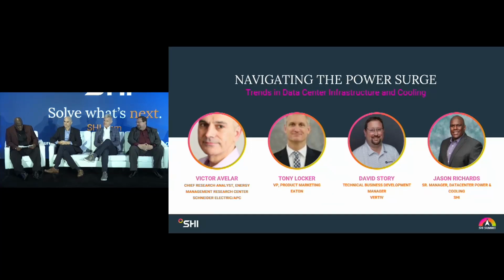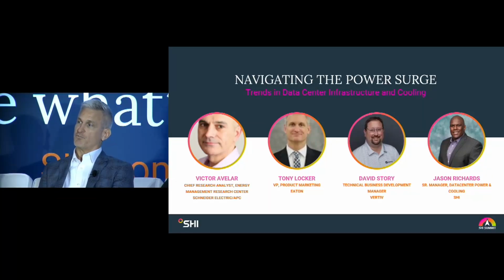Perfect. So we can jump into some of the questions we have here. The first one's for you, Tony. How does the rise of artificial intelligence impact data center power consumption and heat distribution? Right. As everyone in the room knows, the AI server has GPUs, which are a much more advanced chip, and it draws a lot more power than a traditional server, in the neighborhood of up to 20 times in some instances. That causes a ripple effect throughout the entire power stream, all the way up to the source.